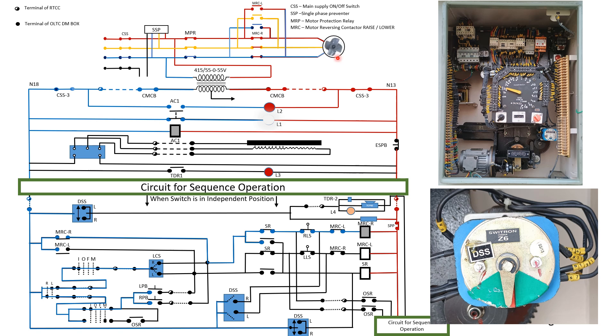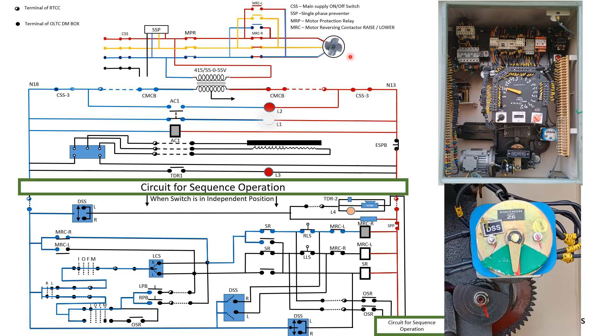Now, how will the motor stop rotating? There is a special provision — the DSS switch situated here. We will understand the working of this DSS switch and how the cutoff is provided to the motor once the tap position has changed. Below this DSS switch there is a special plunger which rotates with its shaft at different positions, and because of this DSS switch, once the tap position has changed, the motor will stop rotating.